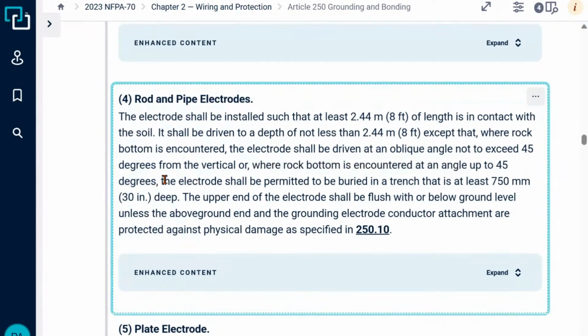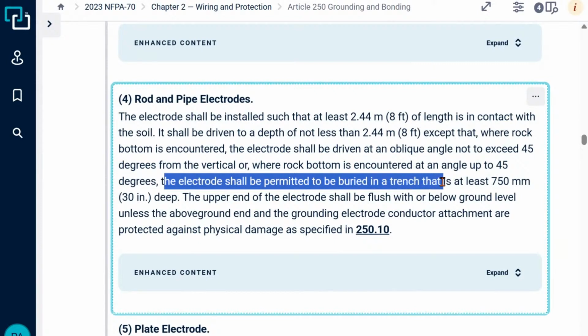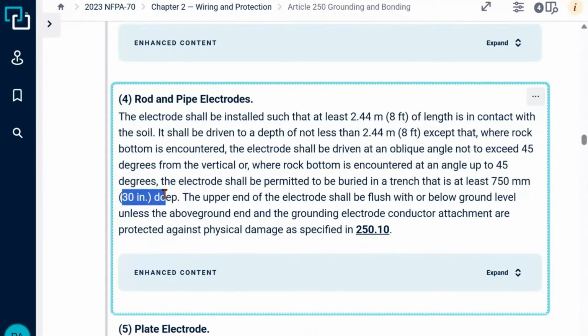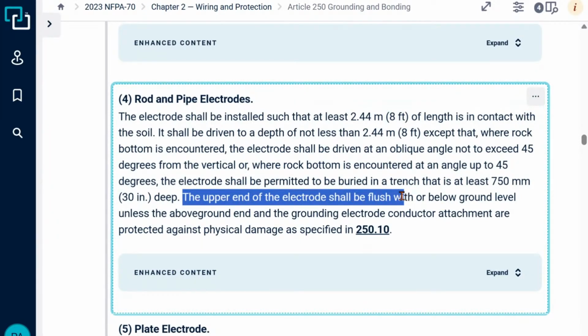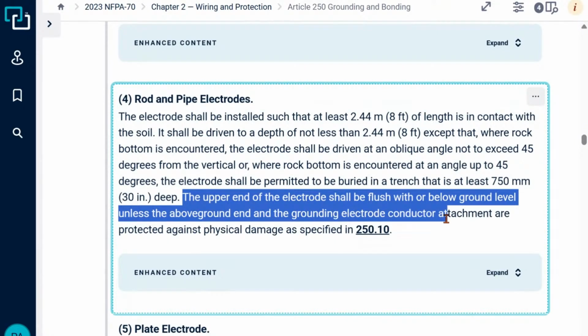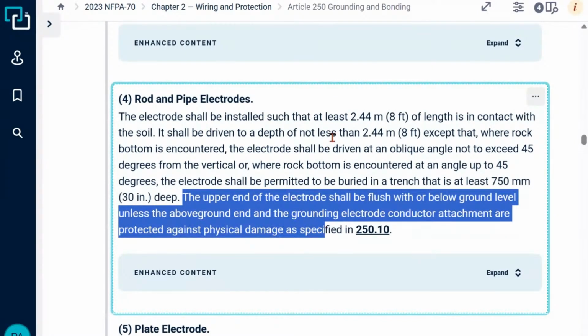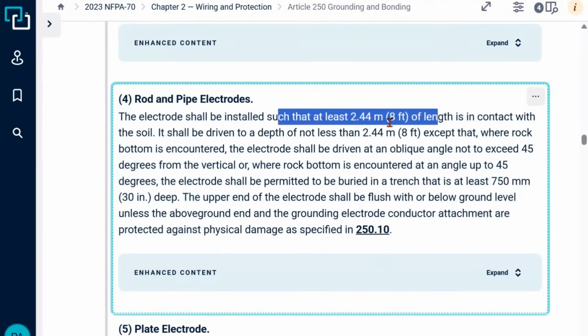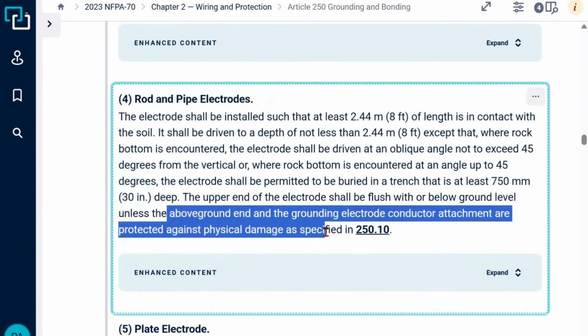It says then the electrode shall be permitted to be buried in a trench that is at least 30 inches deep. And this is a part that everybody misses. The upper end of the electrode shall be flush with, not protruding beyond, flush with or below grade level, unless the above grade end of the grounding electrode conductor attachments are protected against physical damage. Of course, you still have to have 8 feet in contact with the earth, so any part of it sticking above the ground would technically be a violation of this part of the rule. But let's say you're using a 10-foot ground rod and you've got 2 feet sticking up. Well, that's okay if you've got 8 feet driven into the earth, but you're going to have to protect the portion that's sticking out of the earth. That becomes more trouble than it's worth, right?